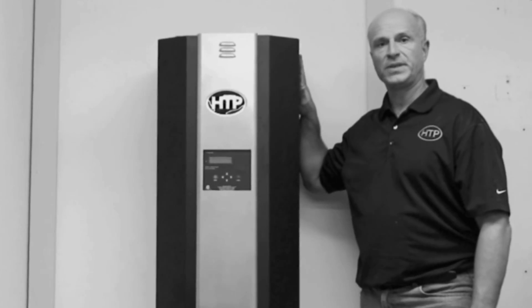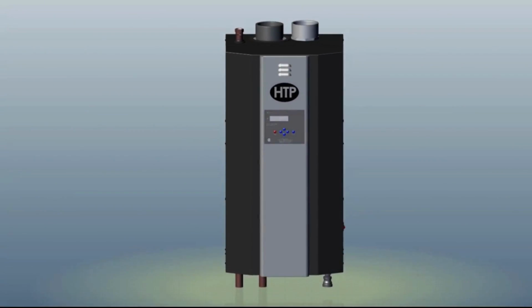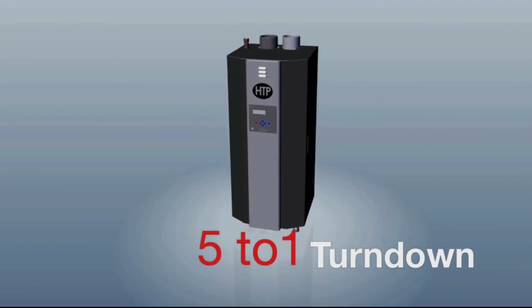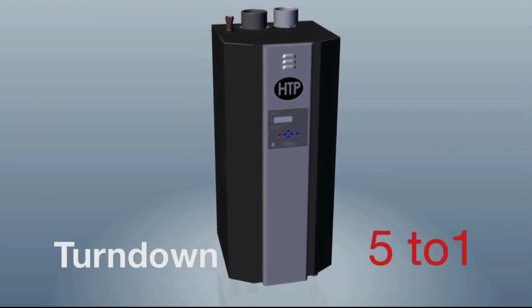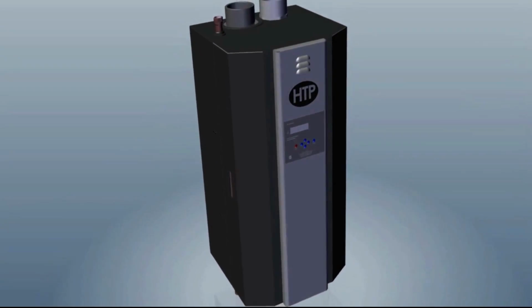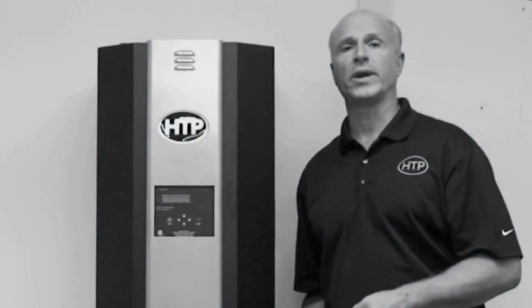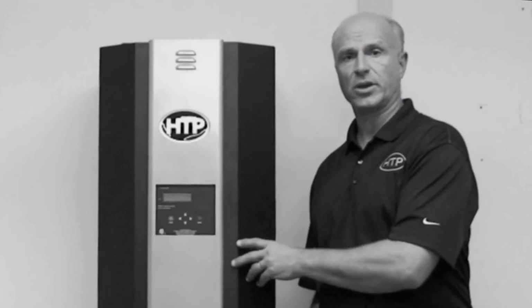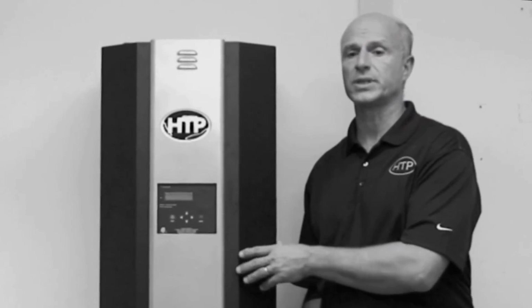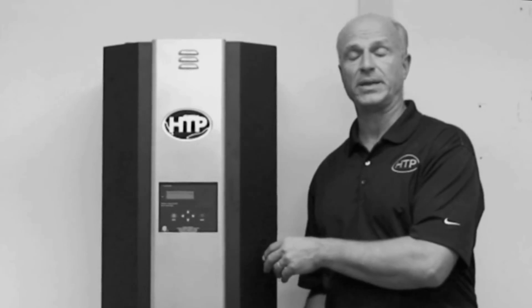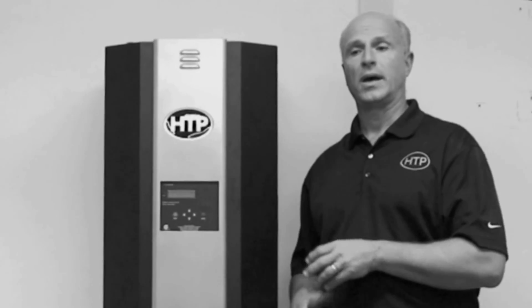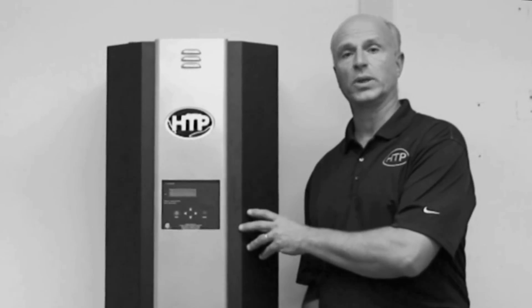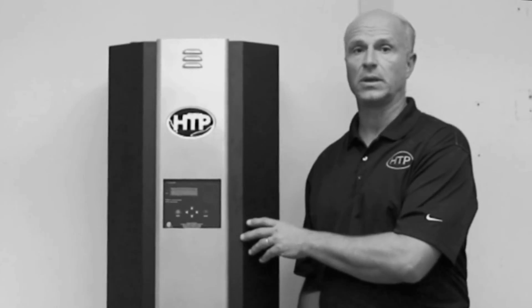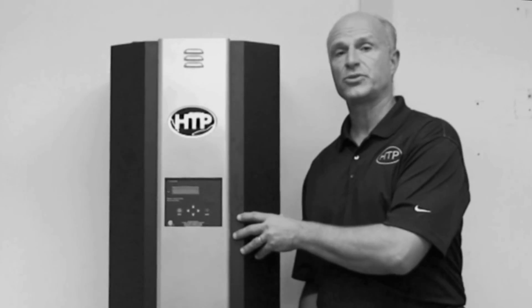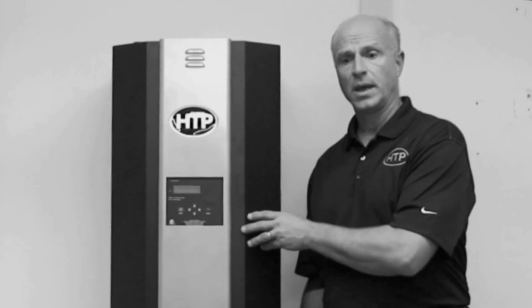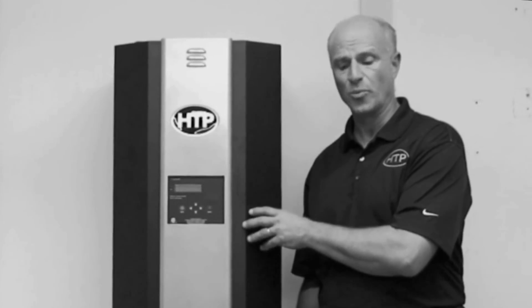Main features of our EFT Elite Fire Tube Boiler. The fire tube boiler has a really good turndown. Its combustion turndown is 5-to-1. Plus, the volume of the heat exchanger provides very low pressure drop in your system. So if you have minimum flow rates that you could achieve in your job, there's really no need to go primary, secondary piping with this, because the boiler won't short cycle if it has proper flow through based on its overall firing rate. So the nice thing about the fire tube is it will allow for smaller pumps. It will allow for easier installation, easier retrofit, and it will avoid a lot of additional piping and additional controls that you would probably need with other low mass boilers.